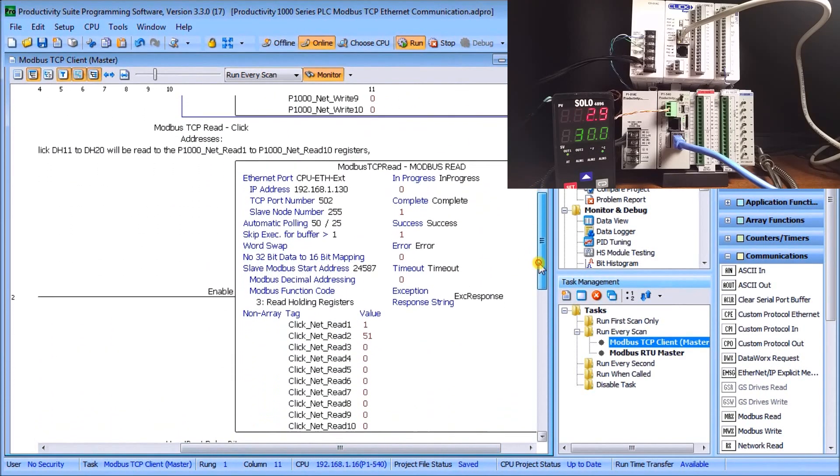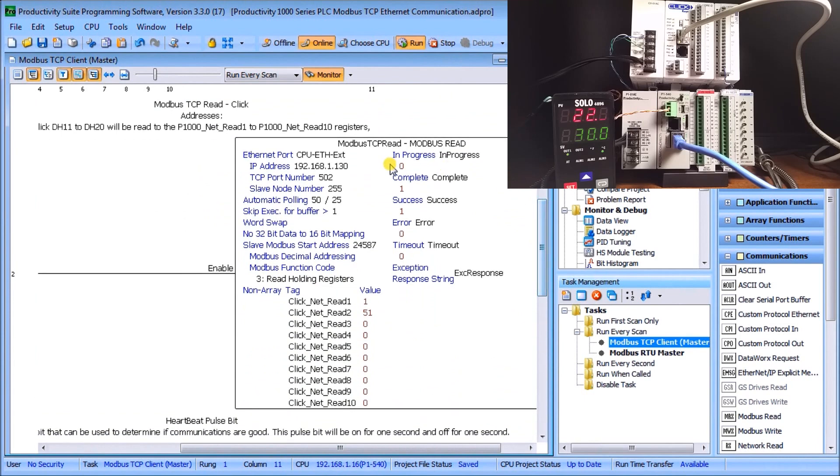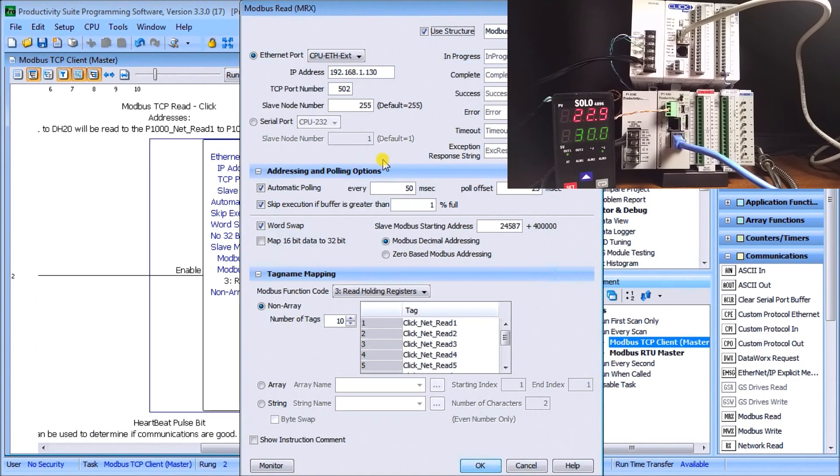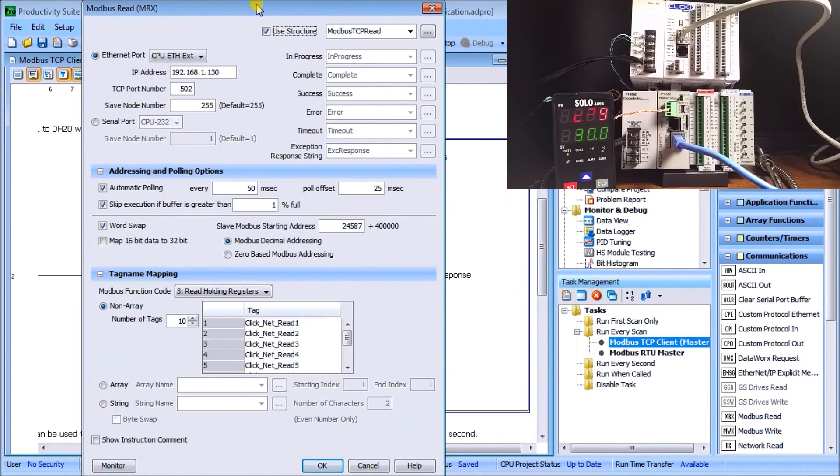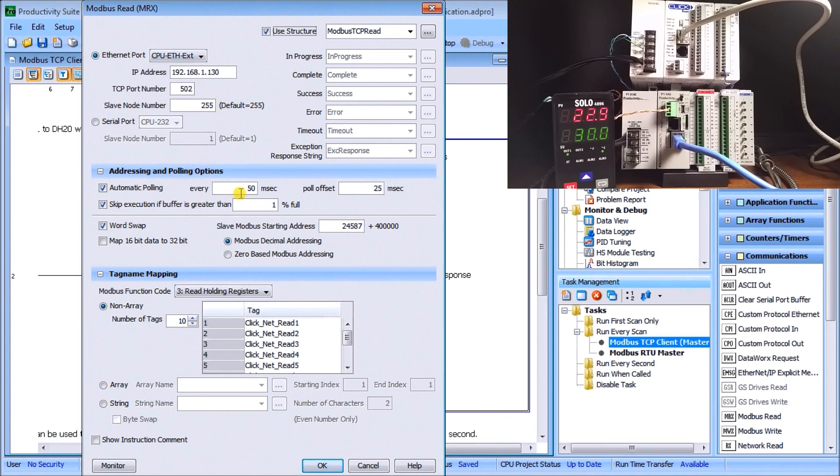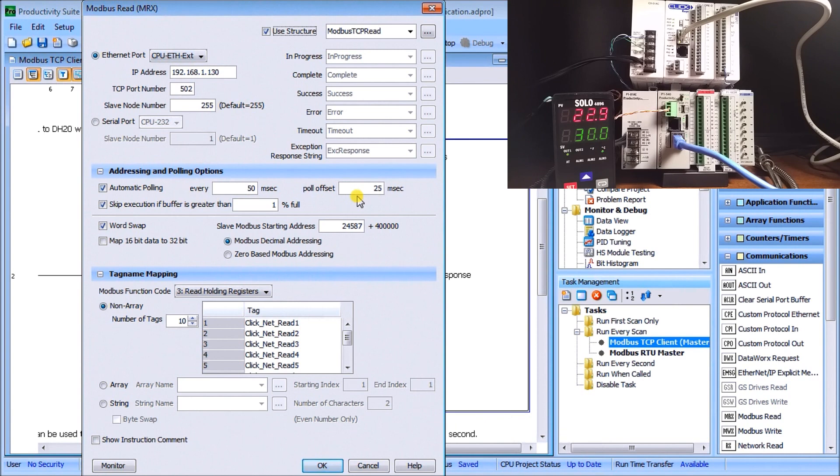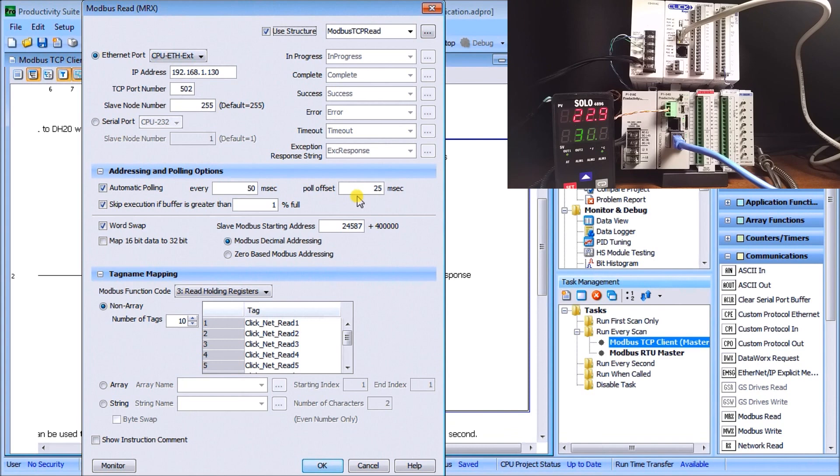Going down on the read, again when we click this we'll get up the structure and I just created another structure here for our Modbus Read. We're going to set up our Ethernet port again and the same address as before for our Click. This time we're going to turn on our automatic polling again, every 50 milliseconds, which is about 20 times a second that we're going to be updating. The poll offset this time is 25 milliseconds. If we think what's happening is as soon as it starts up, it will do our write first, then 25 milliseconds later it'll execute this, and then every 50 milliseconds afterwards. So I've staggered my communication links.